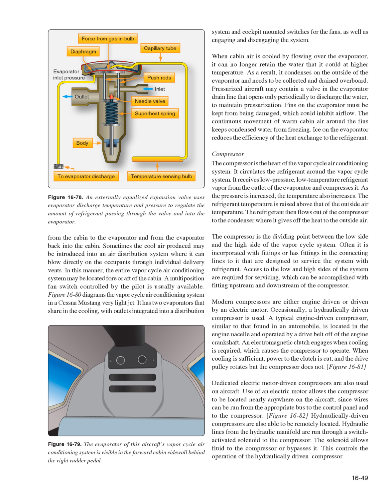When cabin air is cooled by flowing over the evaporator, it can no longer retain the water that it could at higher temperature. As a result, it condenses on the outside of the evaporator and needs to be collected and drained overboard. Pressurized aircraft may contain a valve in the evaporator drain line that opens only periodically to discharge the water, to maintain pressurization. Fins on the evaporator must be kept from being damaged, which could inhibit airflow. The continuous movement of warm cabin air around the fins keeps condensed water from freezing. Ice on the evaporator reduces the efficiency of the heat exchange to the refrigerant.